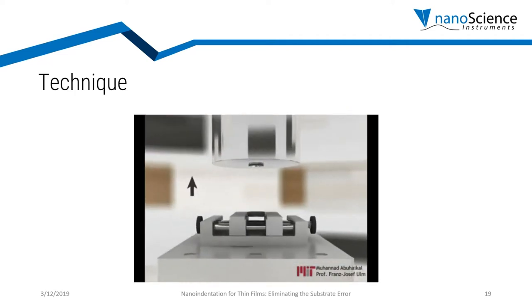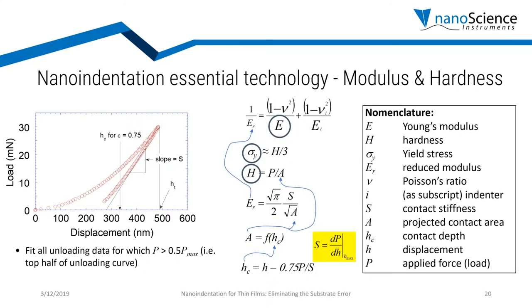With this load and displacement data, we use contact mechanics — we know very well how one material compressing on another works, and knowing the total deformation, we can precisely figure out the properties of the material we are pushing on. This is all real physics, not interpolation. Using this superior physics in our indenters, we calculate properties such as Young's modulus, hardness, and many more.